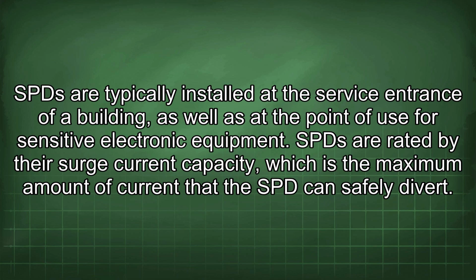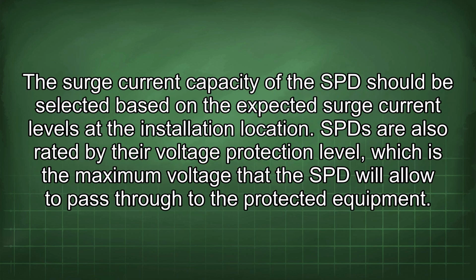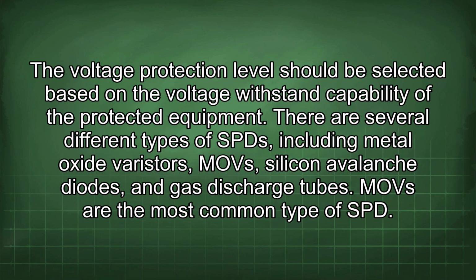sensitive electronic equipment. SPDs are rated by their surge current capacity, which is the maximum amount of current that the SPD can safely divert. The surge current capacity of the SPD should be selected based on the expected surge current levels at the installation location. SPDs are also rated by their voltage protection level, which is the maximum voltage that the SPD will allow to pass through to the protected equipment. The voltage protection level should be selected based on the voltage withstand capability of the protected equipment.